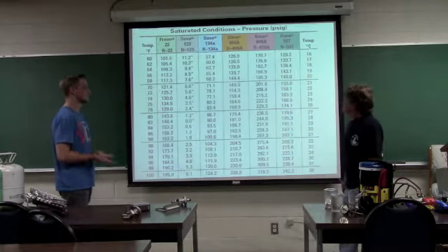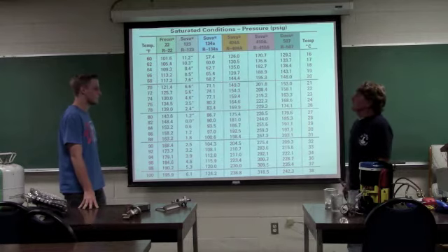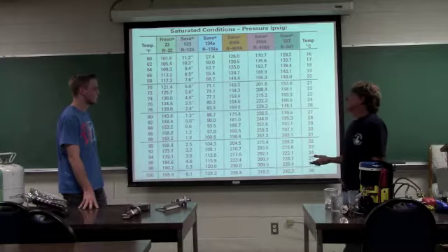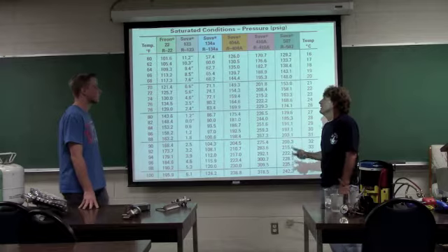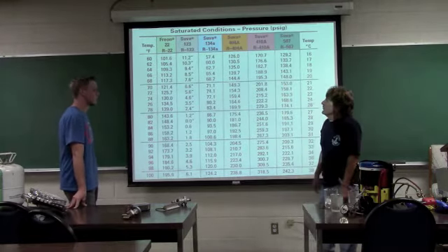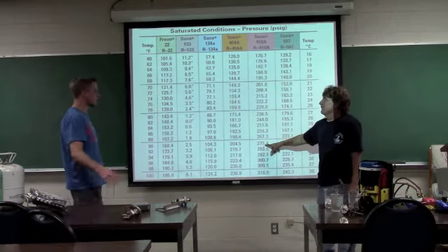Always. So if I look at here, and let's say that I have a package rooftop unit, it's 60 degrees outside, I have a standard efficiency condenser, which means that it's designed for 30 degree refrigerant, it's gotta be 30 degrees above ambient, and my temperature is 60 degrees outside. If I add 30 degrees to that, 90 degrees. So at 90 degrees for R410A, I've got 275.4.